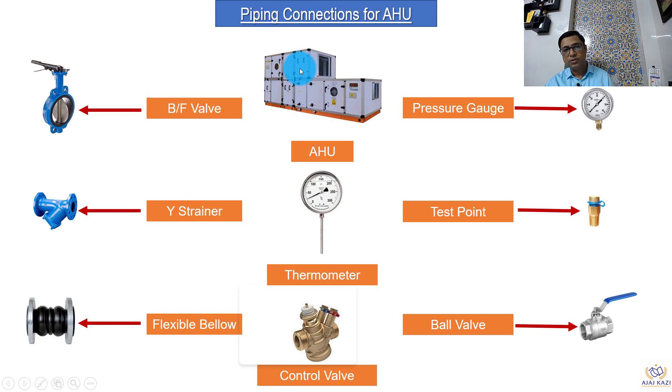This is how the air handling unit looks. First, we have a butterfly valve — the purpose of the butterfly valve is to provide isolation of the unit from the other set of piping. Then we have a Y strainer, to remove dirt and particles from the pipes. Then we have flexible connections — these are flexible bellows to avoid any vibration coming from the air handling unit to the pipes and then to the building structure. We also have a thermometer to check the temperatures in and out of the piping.